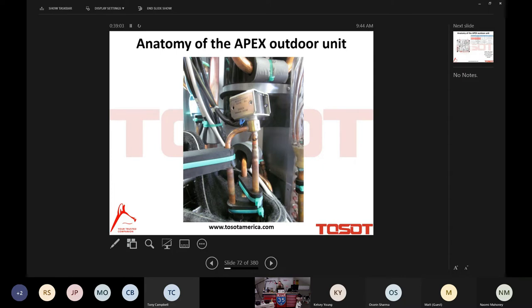Guys, what's important for you to understand, and even more important for your customers to understand, is that this system, the Apex system, is very much two systems in one. And I know it's a split system, right? Duh, so it's kind of obvious. But what I mean is that internal to the outdoor unit, it's very much two separate systems. As you'll see in just a moment, the outdoor unit of the Apex has two EEVs, electronic expansion valves, and what you already saw of the indoor unit is that it has a TXV. Well, how the heck does that work? Why do we need three expansion valves, two of them electronic and one thermally actuated? Well, this is why: because it's very much two separate systems. When the system is in the heating mode, the two EEVs of the outdoor unit are doing the heavy lifting, so to speak.